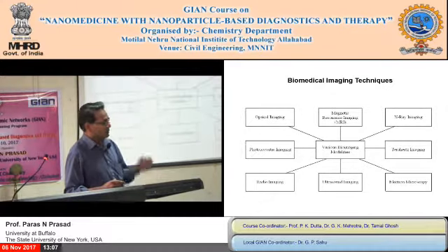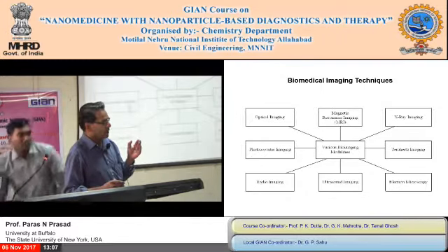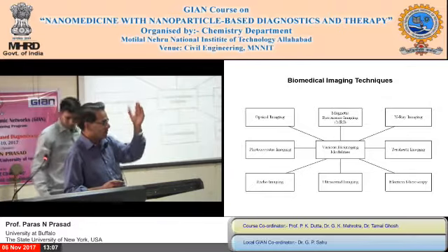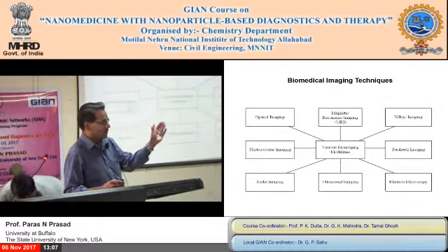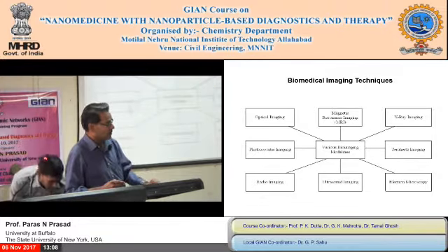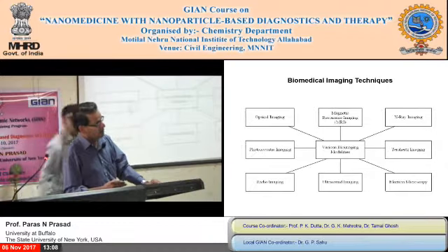That means your data acquisition is going to be a little bit slower. However, you can take advantage of another technique called time gating. With time gating, you can reject unwanted signal which is very fast. So for the first 100 nanoseconds you don't collect any signal, and you collect only after that, so you only see phosphorescence. That has an advantage. So one limitation is data acquisition.